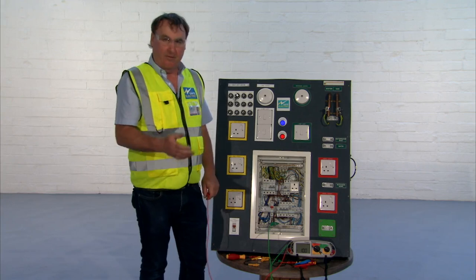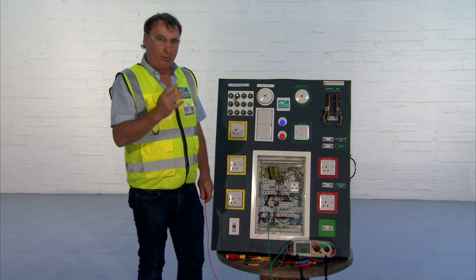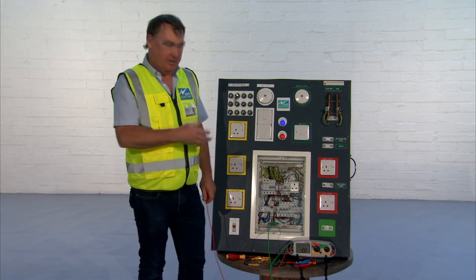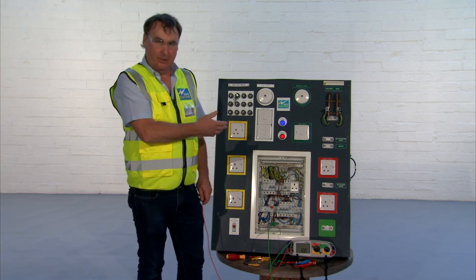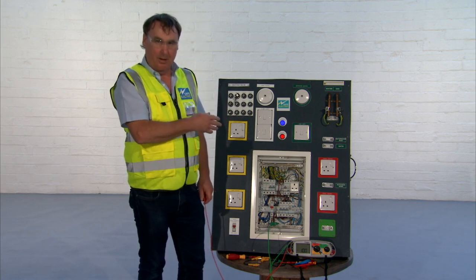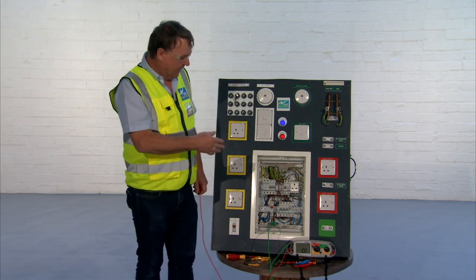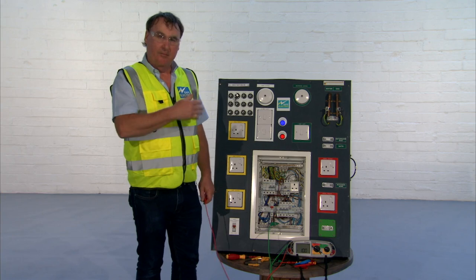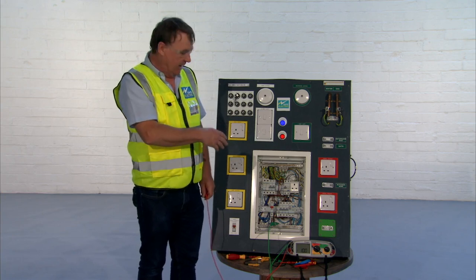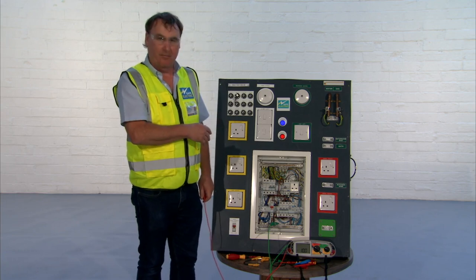We have now confirmed using the new voltage method that there are no erroneous connections between circuits in this electrical installation. That means that each circuit is fed by one MCB and one MCB only. The principle is, if you had a second MCB feeding one of the circuits, it would have remained at 227 volts, even when we turned off the circuit breaker.